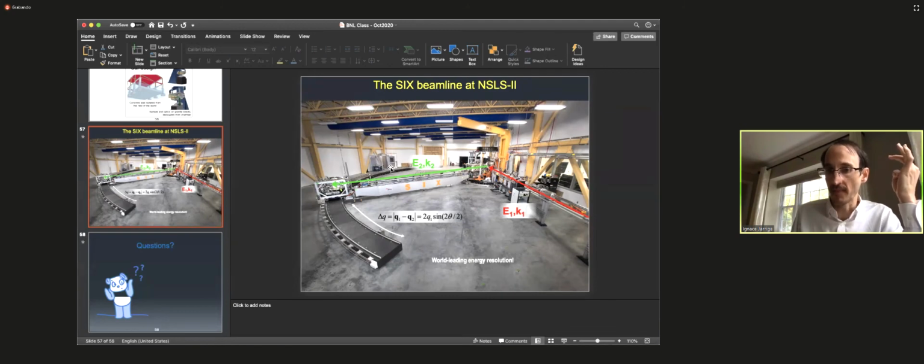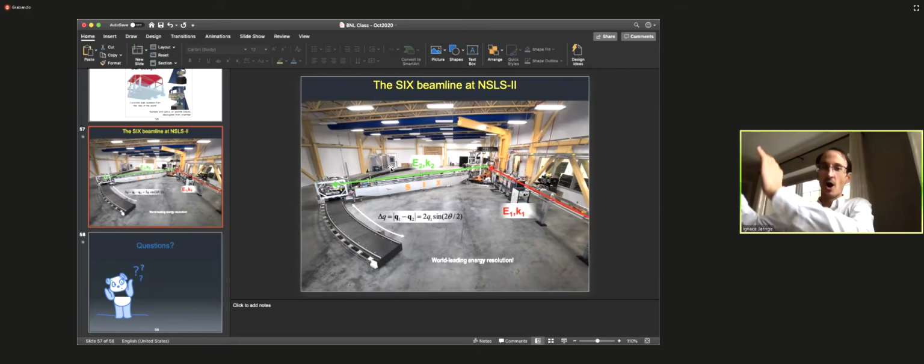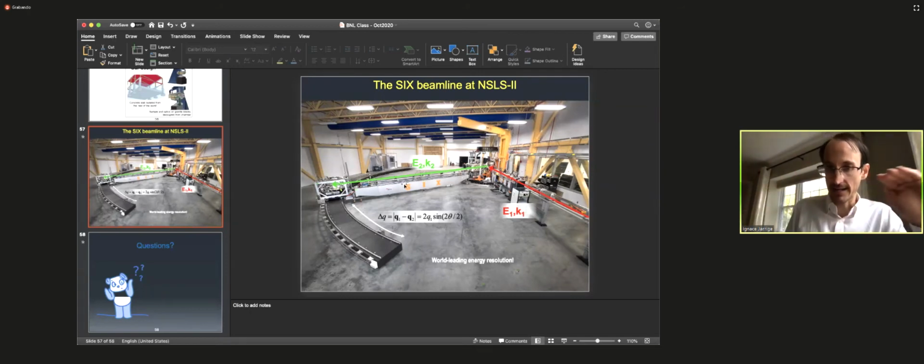But that avoids having the detector going up and down. Vibrations are really avoided by letting things go static at one given angle. And we have here the arm that couples this monochromator to the detector, that's pulling things together, right? There's a motor here and one there, and it rotates. It helps bring the two extremities in concert when it moves.